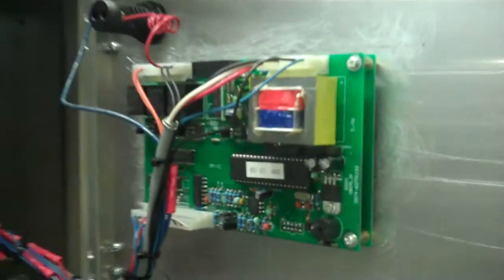And you can hear just then the fan and the compressor turned on. That was not just the fan. The compressor is running right now too. This here is a single-phase transformer which takes one leg of the 460 volt and steps it down to 220 single-phase to give you the controller power.